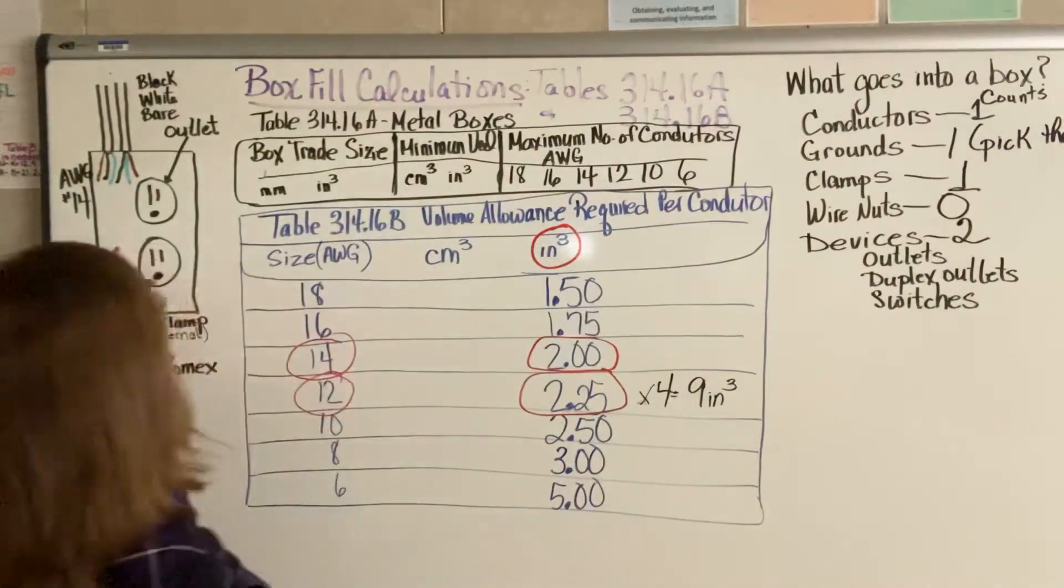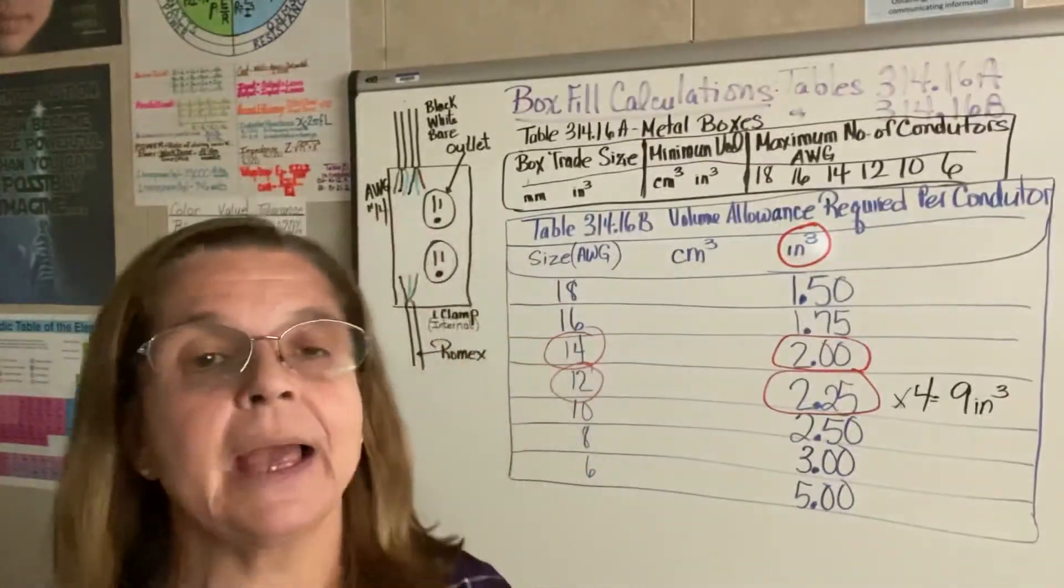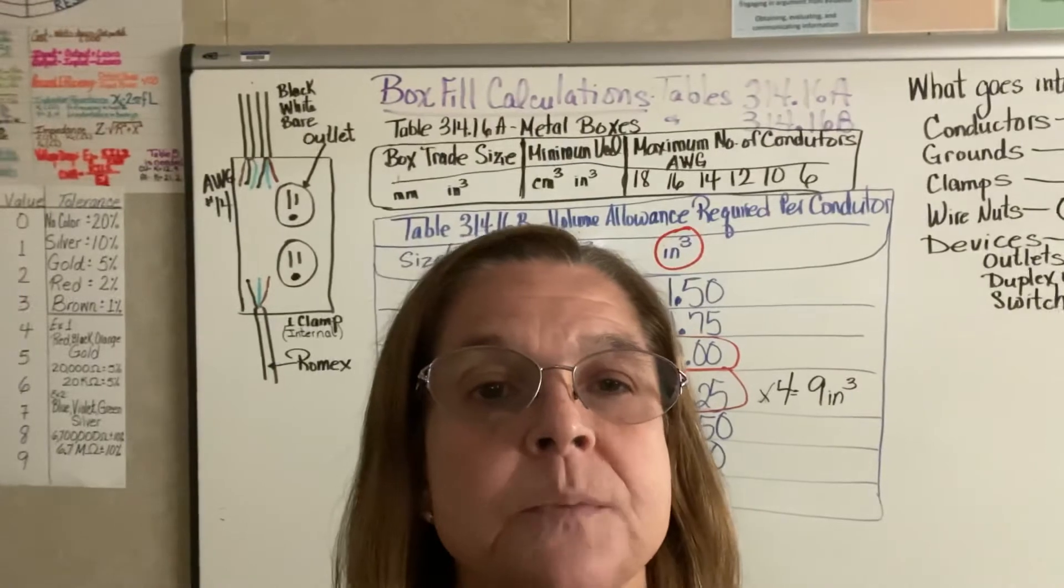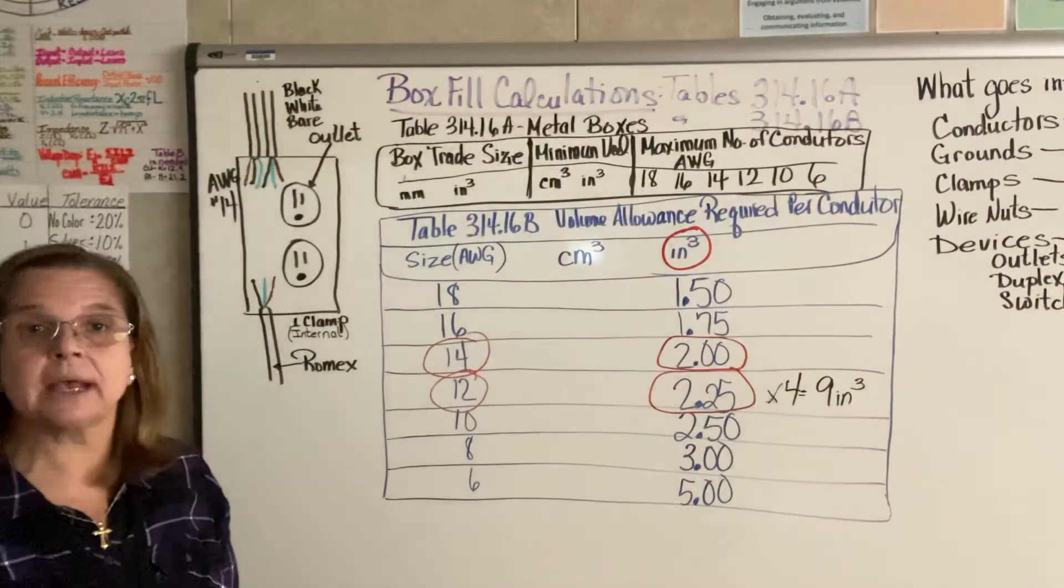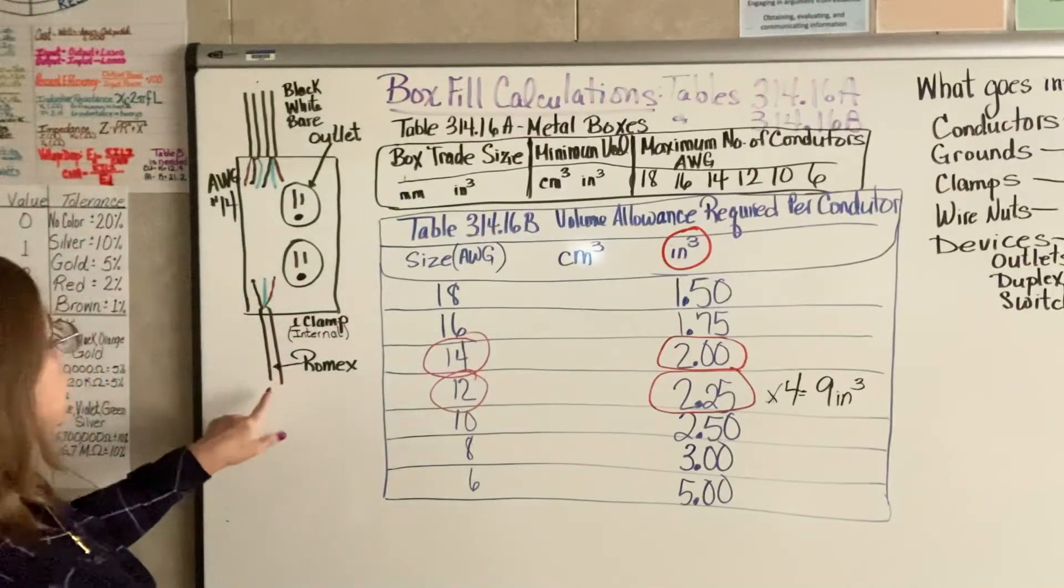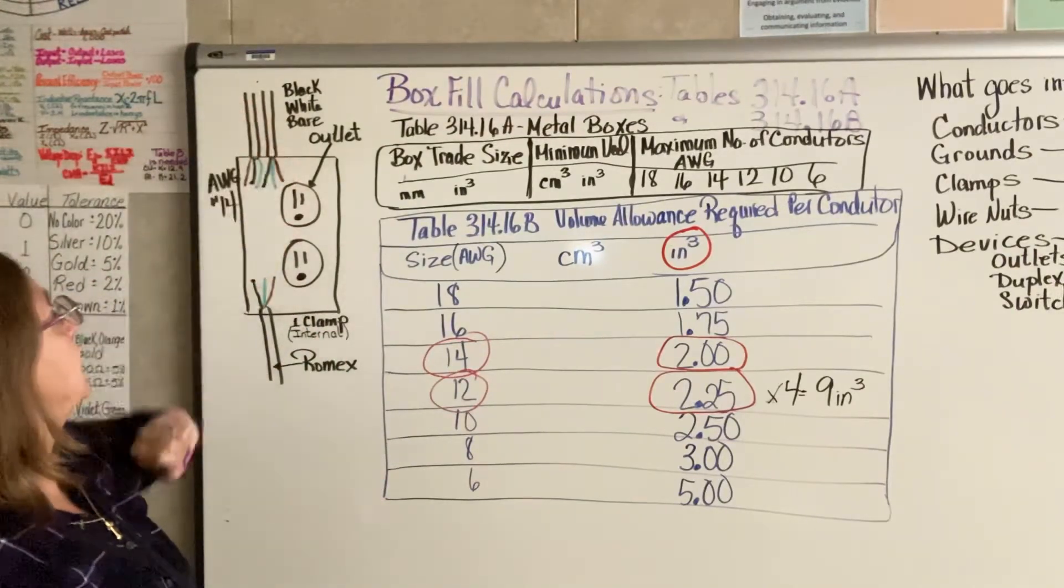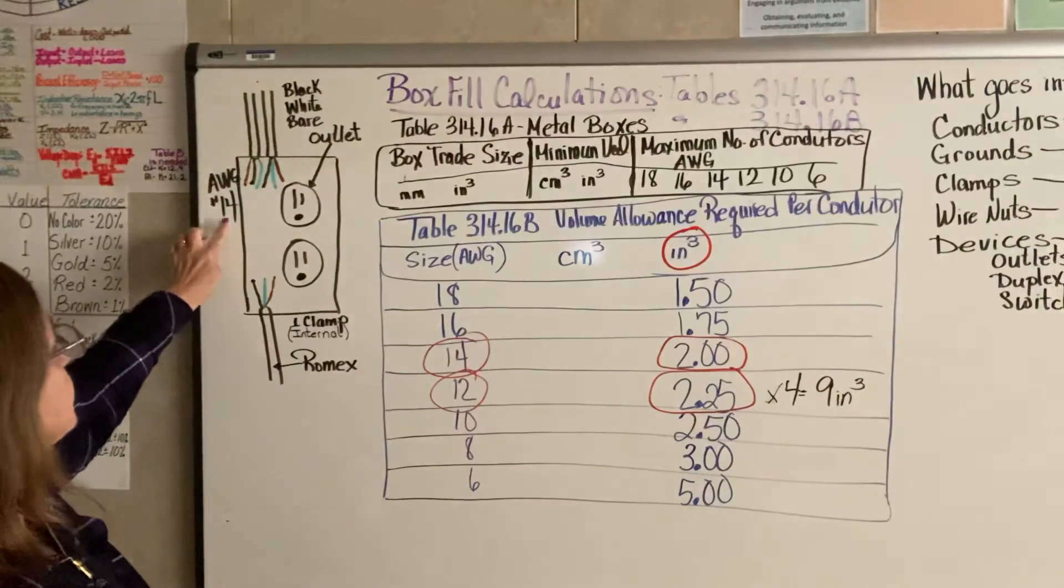So now, over here on the other side, I have an example for us to work through. I have a picture of an outlet here. This particular outlet has an outlet put inside. So in this box, we're going to put an outlet. You can see there's a Romex coming in from the bottom, two going out on the top. And for residential, 14 is a very common wire size. So I've chosen to use size 14. I do have an internal clamp, a couple of wire nuts in there.